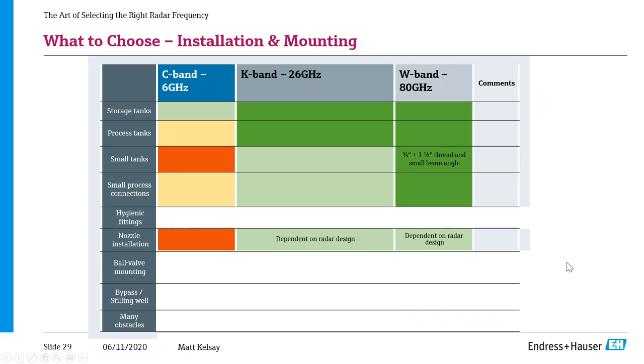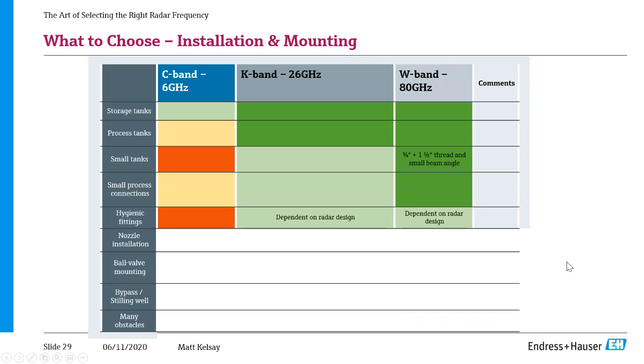For hygienic applications, this is really more dependent on radar design, not necessarily the frequency. However, in our C-band portfolio, we don't have any hygienic designs, which is why you see that listed as red. In both the K-band and W-band, we do have hygienic designs available. Some are and some aren't, so that's why it's listed as that light green, but we do have solutions available.